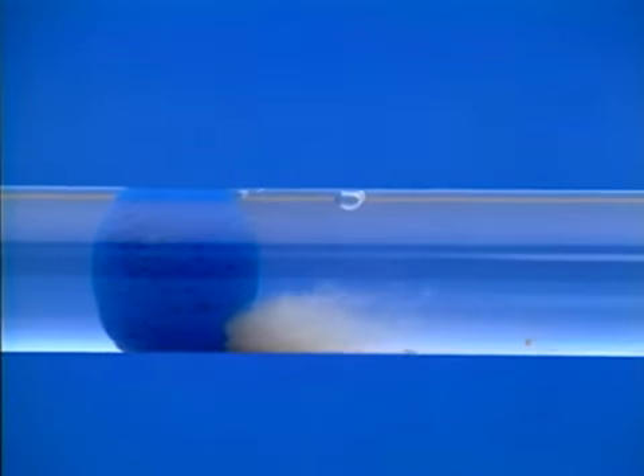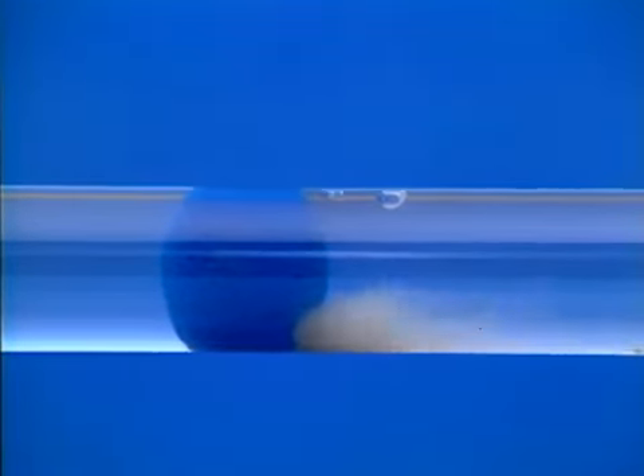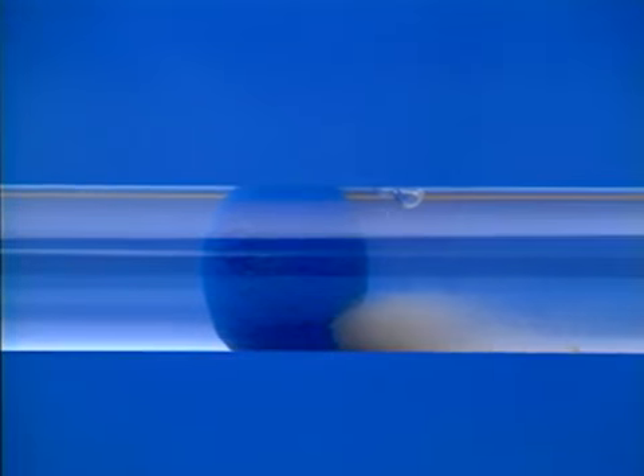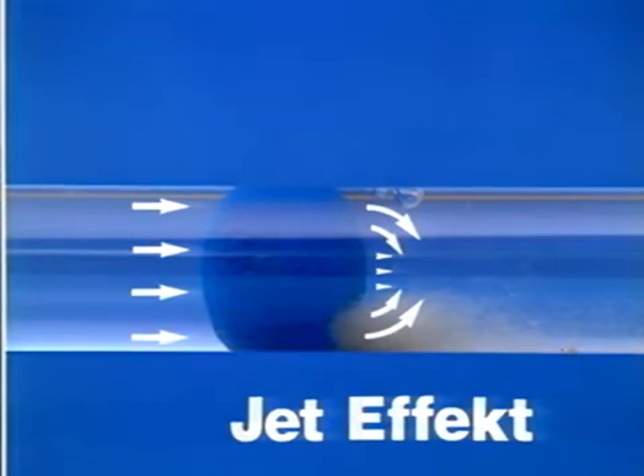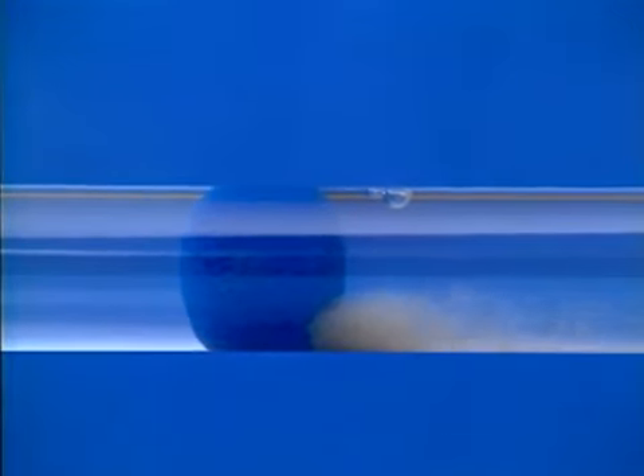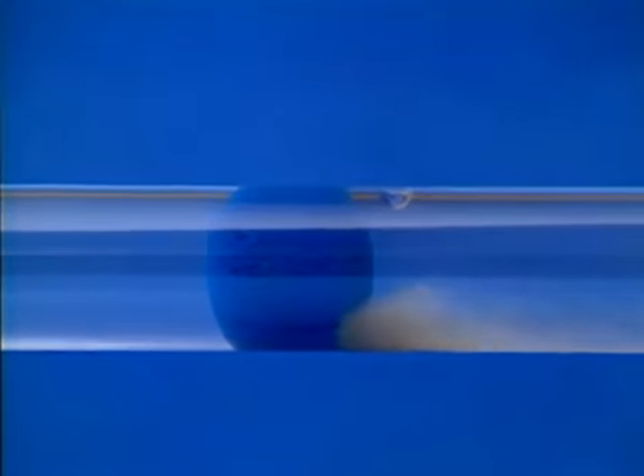The water forces the balls through the tube. As a result, the speed in the boundary layer in front of the ball rises sharply, generating a jet effect that dislodges sand or slime deposits from the tube wall and flushes them out of the tube.